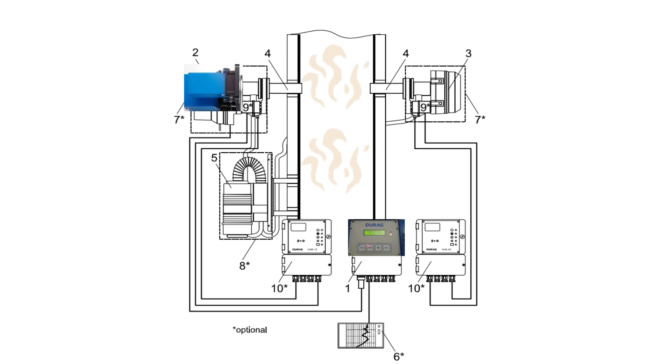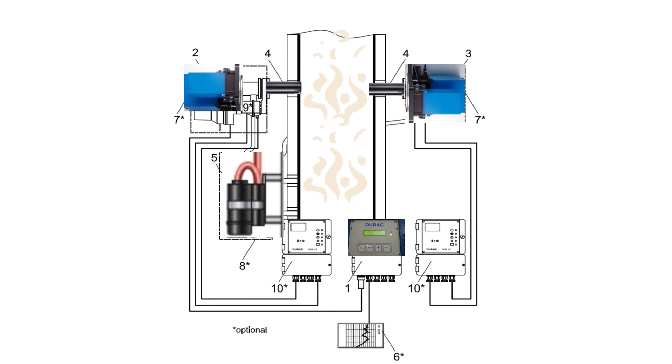Number three is reflector DR-290. The light that hits the reflector is returned parallel to the incoming light and back to the transceiver. Number four is stack flange DR-280E. This is used to support the monitor on the stack. Number five is purge air unit. This protects the monitor from contamination on the external optical surface and keeps the unit from overheating.